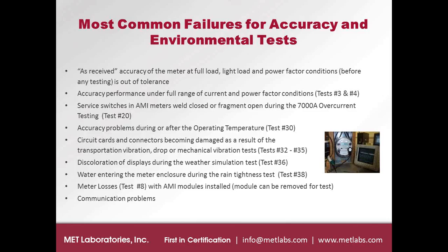Occasionally, running the full range of the load performance testing or the power factor conditions, tests 3 and 4, we'll see either the low end or the high end cause problems in terms of not meeting the limits given in the standard. Again, with the service switches, we have seen problems with the overcurrent testing, test 20, where they seize up, and really that 7,000 amp, and that's a 7,000 amp peak overcurrent surge for several cycles. You've got to be able to survive that, so the switches need to survive that.